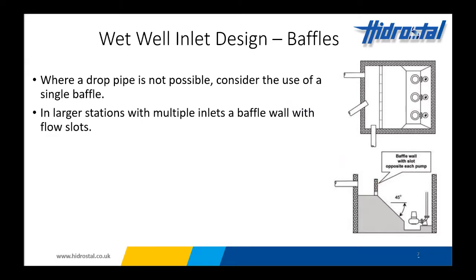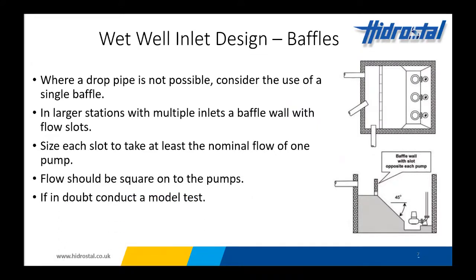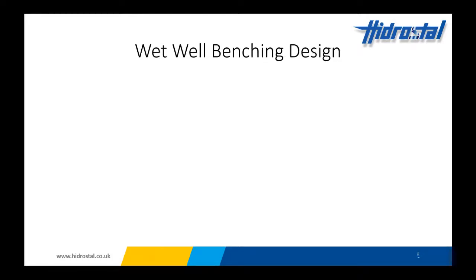And these baffle walls typically have square slots to accept flow. Each slot should be sized to take at least the nominal flow of one pump per slot. And the flow, again, should be square onto the pumps. But if in doubt, it pays dividends to conduct a model test.